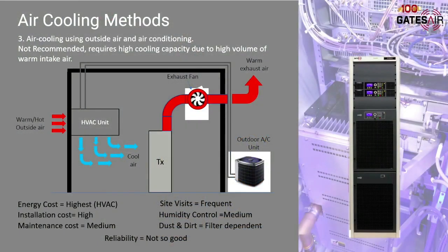Another method is pulling outside air into the room and then through the transmitter, using the room as a kind of buffer, and then out from there, drawing that heat out. So energy costs, well, they're the highest. And the reasoning is because I'm drawing warm air from outside, and it's typically warm, moist air, into the room. Well, my air conditioner then has to work twice as hard because it's trying to dehumidify and cool that warm air coming in. Okay? That room acts like that buffer. The transmitter is going to be happy. It's seeing the cool air because the air conditioner is doing all the work. But your costs are high.